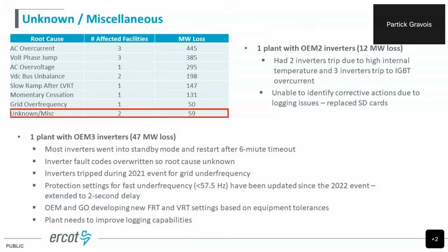And then finally, we had one more plant that lost about 5% of their megawatt. Out of the 80 to 100 inverters they have, about 5 of those tripped. Two were due to a high internal temperature, and 3 were due to overcurrent. They were also unable to identify corrective actions. They are having issues with their SD cards recording the fault codes getting overwritten as well, so they were doing some work there as well.